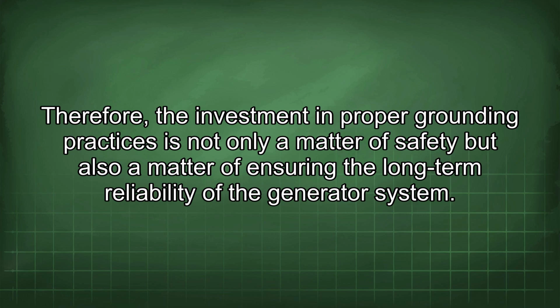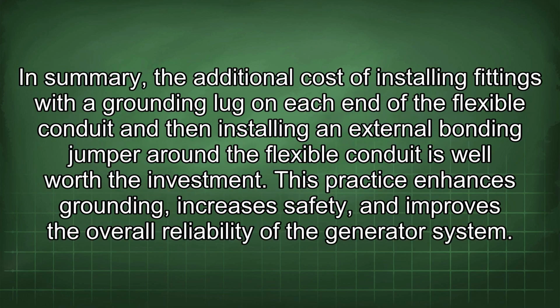Therefore, the investment in proper grounding practices is not only a matter of safety but also a matter of ensuring the long-term reliability of the generator system. In summary, the additional cost of installing fittings with a grounding lug on each end of the flexible conduit and then installing an external bonding jumper around the flexible conduit is well worth the investment. This practice enhances grounding, increases safety, and improves the overall reliability of the generator system.